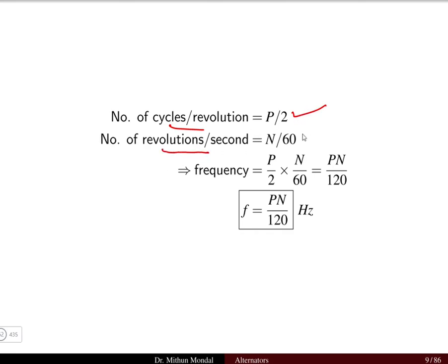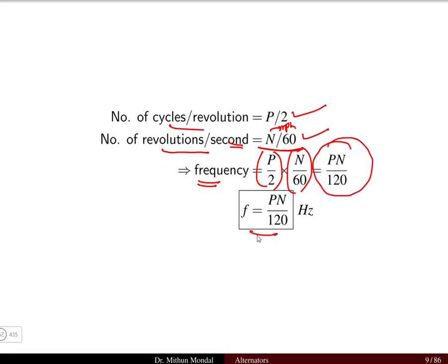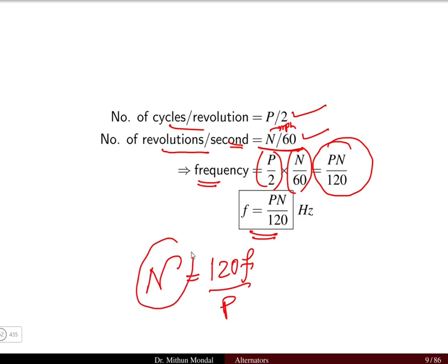The number of revolutions per second is N/60, where N is speed in rpm. Therefore, frequency F = (P/2) × (N/60) = PN/120 hertz. So the speed is N = 120F/P, showing a direct relationship between speed and frequency. When the speed of the rotor increases, the frequency increases proportionally, since the number of poles is fixed by construction.